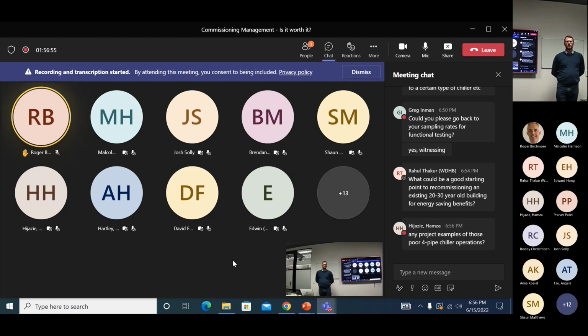Set points being reset. When you've got scheduled set points in your BMS, especially a VAV system, the system tries to schedule down to the highest cooling demand, the lowest temperature it needs to provide, and then all your other VAV boxes go into reheat mode. Often all the sensors are input into the calculation. You just need one sensor to be faulty, and it drives that temperature down to its minimum, and everything else is reheating. Very high energy use.